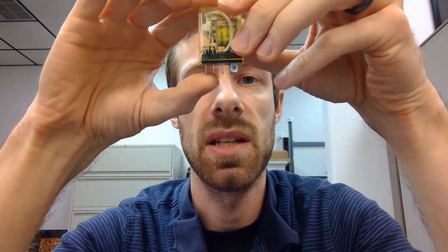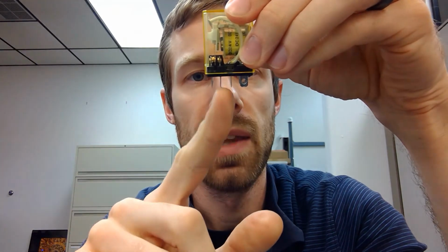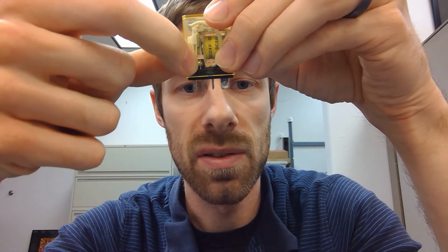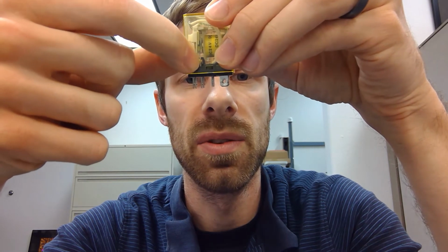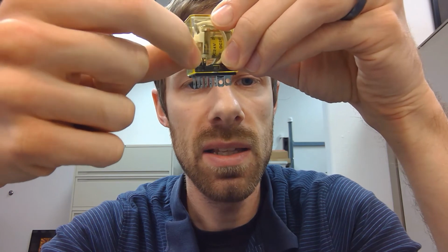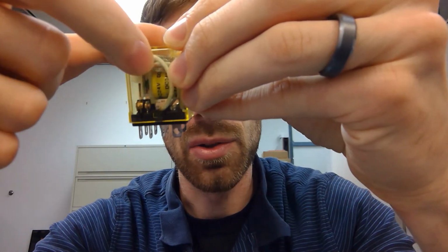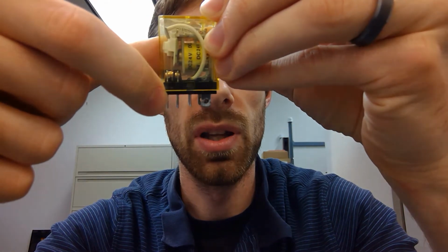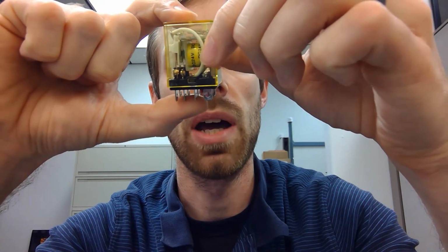That set of contacts has a common terminal. It also has a normally open terminal. That's the middle one, and you can tell because there is an air gap right in there. So it's not connected to that terminal, but this copper tab is connected to the furthest outside terminal. That means that while it's sitting here, unenergized, obviously I'm not powering the coil of this right now, I have an electrical connection between this one with this white wire that's looping up over here and this terminal on the very outside. That's called normally closed because right now the circuit is being connected even without it being energized.